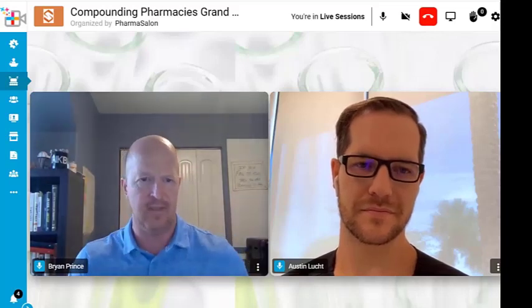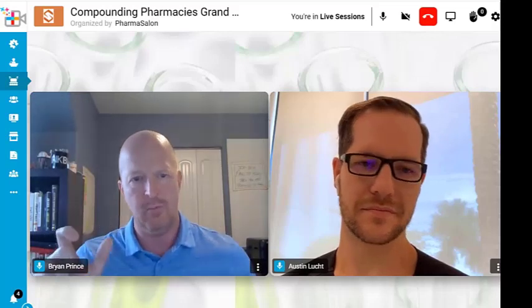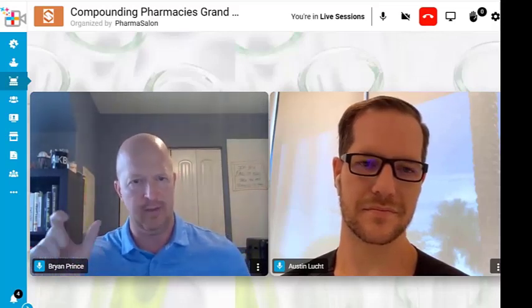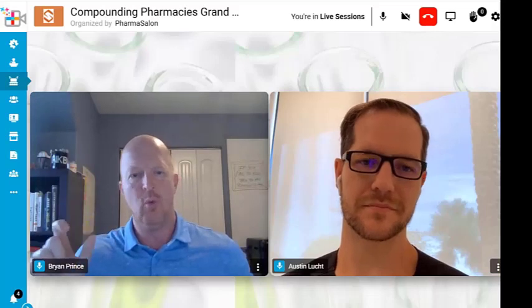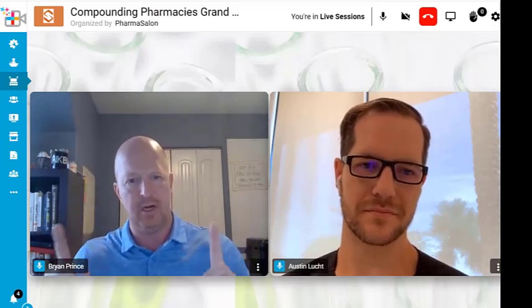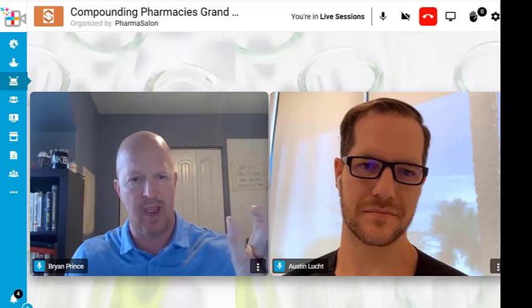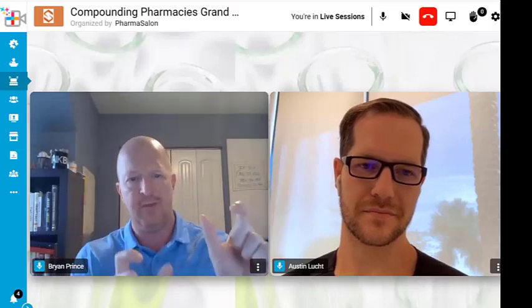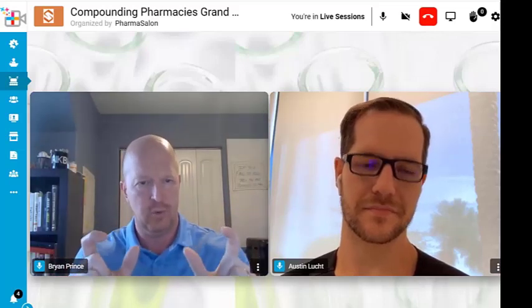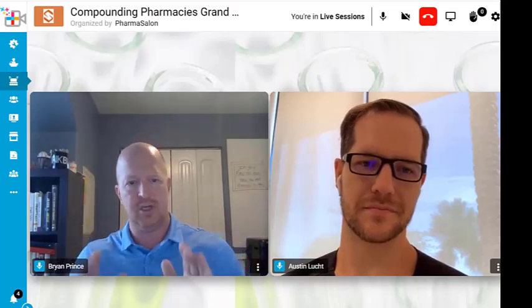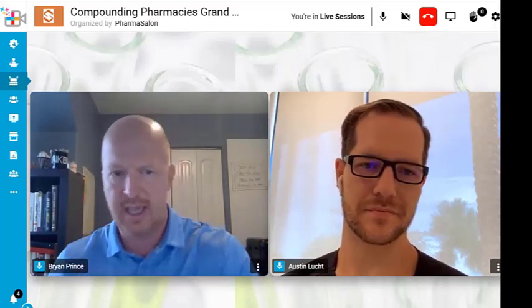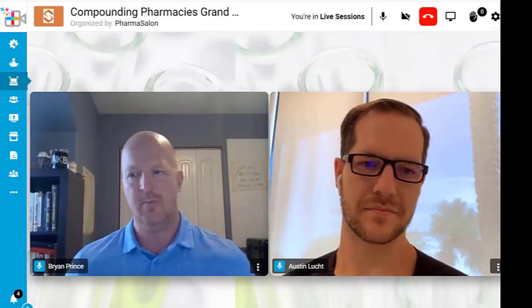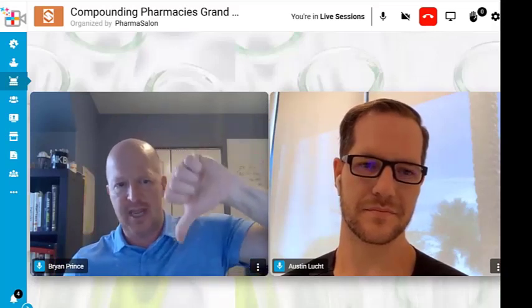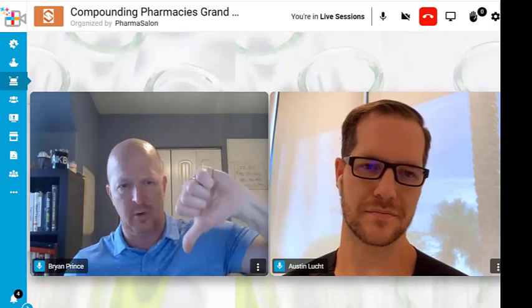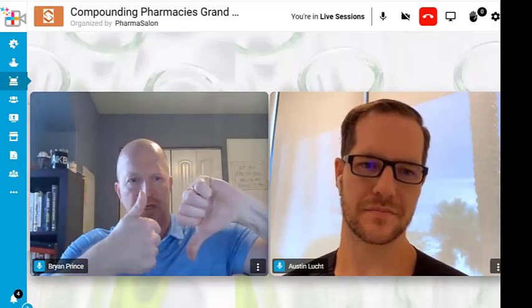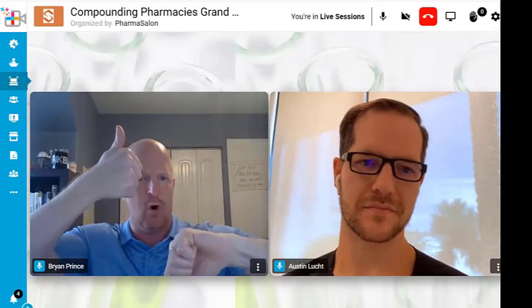Now there's another caveat to that. And the should is that that room should be under 60% relative humidity, right? And so you want to spec out as part of the compressor unit that is going to target 64F or 65F and 50% RH, which is relative humidity. So there's an inverse relationship. If this is wrong, this is going to kill you financially, right? And so as you start driving that thermostat down, those coils inside that unit can only wring out that moisture so fast. So you're starting to lose control of relative humidity. They're going to start to walk away from each other.